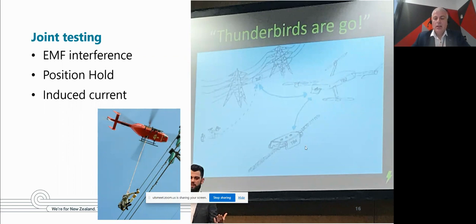What we call a ductor, to measure the resistance of the joints and make sure the sleeves have been centered within those joints, and we're checking for degradation. That's obviously A, expensive, and B, relatively dangerous, and C, it's really hard to get to the center phase.